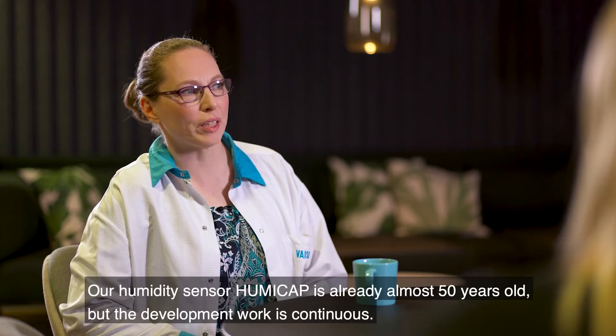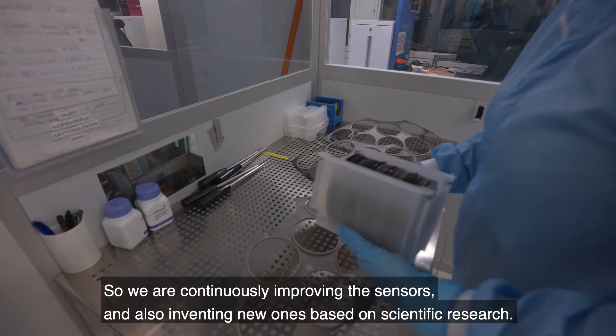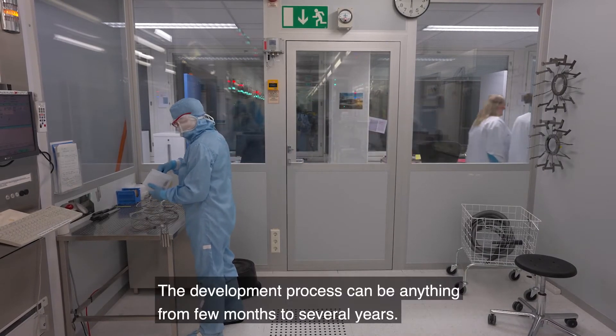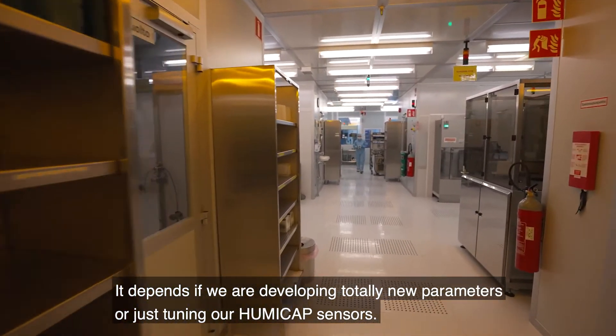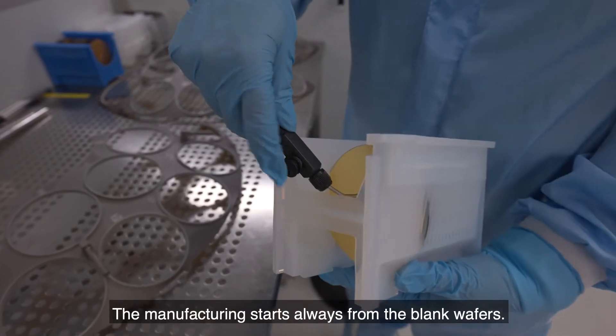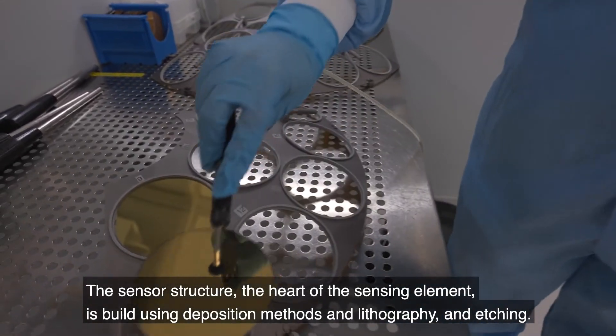Our humidity sensor HUMICAP is already almost 50 years old, but the development work is continuous — we are continuously improving the sensors and also inventing new ones based on scientific research. The development process can take anywhere from a few months to several years, depending on whether we are developing totally new parameters or just tuning our existing HUMICAP sensors. The manufacturing always starts from blank wafers, and the sensor structure — the heart of the sensing element — is built using deposition methods, lithography, and etching.